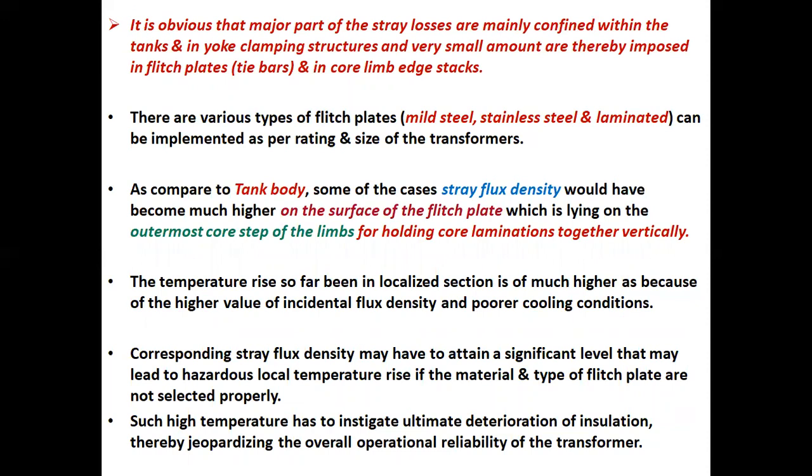There are various types of flitch plates such as mild steel, stainless steel, and laminated type, which can be implemented as per rating and size of the transformers. As compared to the tank body, in some cases stray flux density would become much higher on the surface of the flitch plate lying on the outermost core steps of the limbs for holding core laminations together vertically. The temperature rise in the localized section is much higher because of the higher value of incidental flux density and poorer cooling conditions.